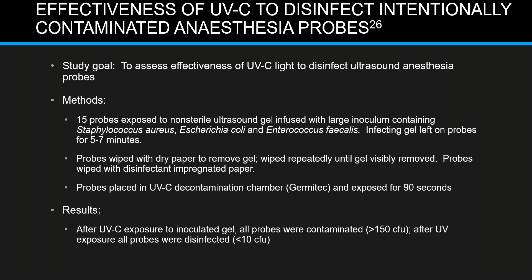The probes were wiped dry with paper to remove the gel, and they were wiped repeatedly until the gel was visibly removed. And then they were wiped with a disinfectant-impregnated paper. The probes were placed in a UVC decontamination chamber by Germitec and exposed for only 90 seconds. Before UV exposure, all probes were contaminated. After UV exposure, all the probes were disinfected. So there we have a demonstration that the UVC was effective in disinfection.